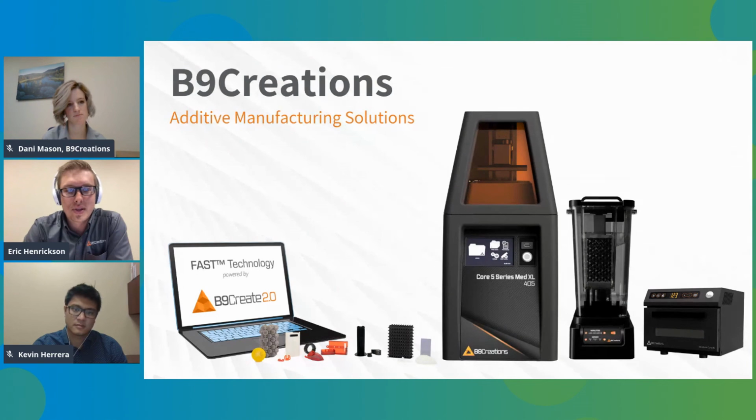The landscape right now in terms of regulatory is that the end device manufacturer has to certify their entire process, essentially. In the future, what we think is going to happen is that's going to be broken up a little bit, so you'll be able to prove medical device compliance all through your manufacturing process chain, down to the bottom, where you will have less burden at the end of the process. So a big reason that we went to getting the compliance on the device was future proofing.